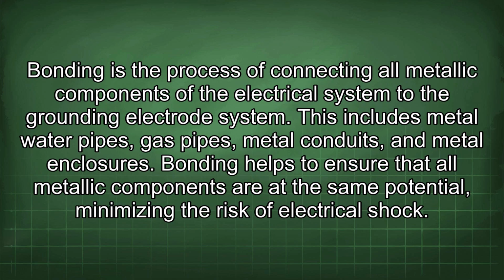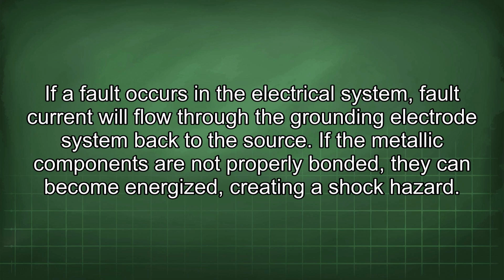Bonding is the process of connecting all metallic components of the electrical system to the grounding electrode system. This includes metal water pipes, gas pipes, metal conduits, and metal enclosures. Bonding helps to ensure that all metallic components are at the same potential, minimizing the risk of electrical shock. If a fault occurs in the electrical system, fault current will flow through the grounding electrode system back to the source. If the metallic components are not properly bonded, they can become energized, creating a shock hazard.